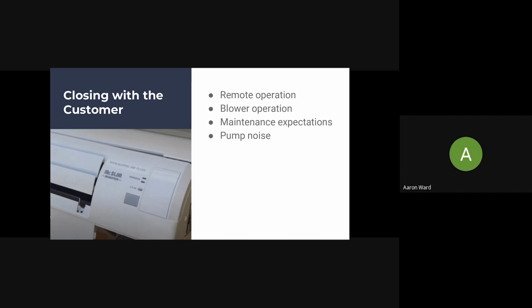I've noticed a lot when having to install the pumps, they have a shutoff and they like you to split the S wire. And I've noticed that whenever you split the S wire and it's longer than about 40 to 50 feet, you run into a lot of communication problems with the unit. So keep that in mind when working with it, and try to find other ways for that automatic pump shutdown when it's not draining, to save water damage, and how to get it to work differently.